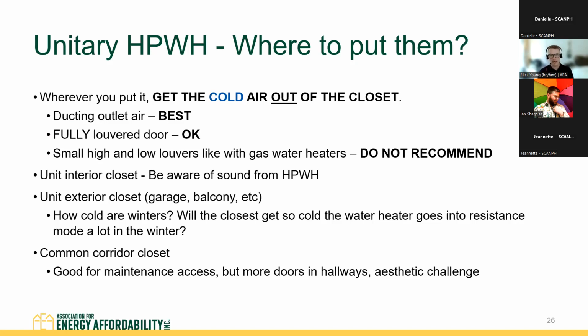When your closet is a meat locker, one, you could get condensation on the inside of your building, which you don't want. Your heat pump is going to run less efficiently because now all of a sudden you have a hot water tank in a very cold environment. Your heat pump may not run in heat pump mode at all, because some heat pumps only run in heat pump mode at or above a certain temperature. It's just a bad situation when the location of your tank type heat pump water heater gets too cold. So you really need to figure out how you're going to get that cold air out of the closet.